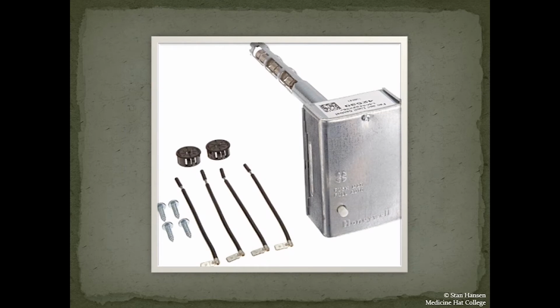The next temperature sensing device we have is called fan control, and it automatically starts and stops the fan for optimum heat circulation. The fan control allows the plenum to heat up before starting the fan to minimize any cold air circulation. And it also keeps running until the plenum has cooled to prevent any heat waste. It uses a normally open bimetal strip located inside the plenum in order to control the fan. Most fan controls also contain a manual override switch, which can be installed in parallel to the fan control to keep the fan running longer, which is good for air circulation and heat balancing.